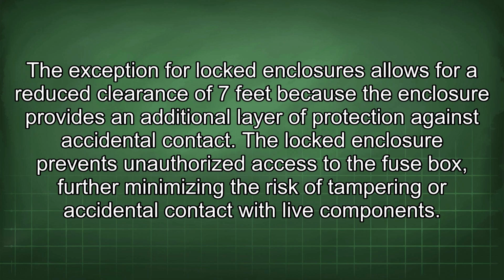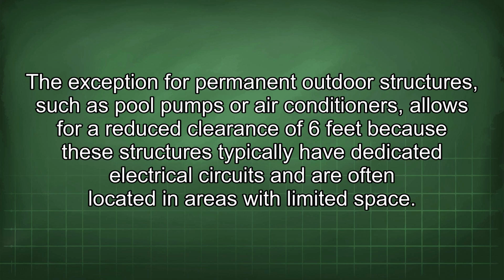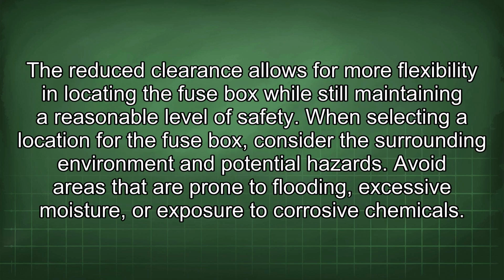The locked enclosure prevents unauthorized access to the fuse box, further minimizing the risk of tampering or accidental contact with live components. The exception for permanent outdoor structures, such as pool pumps or air conditioners, allows for a reduced clearance of 6 feet because these structures typically have dedicated electrical circuits and are often located in areas with limited space. The reduced clearance allows for more flexibility in locating the fuse box while still maintaining a reasonable level of safety.